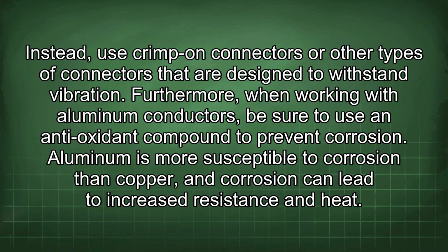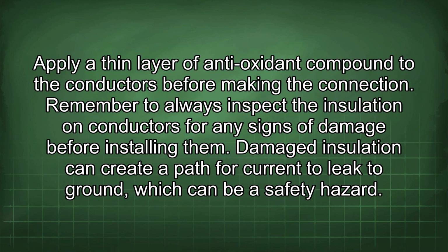Furthermore, when working with aluminum conductors, be sure to use an antioxidant compound to prevent corrosion. Aluminum is more susceptible to corrosion than copper, and corrosion can lead to increased resistance and heat. Apply a thin layer of antioxidant compound to the conductors before making the connection.